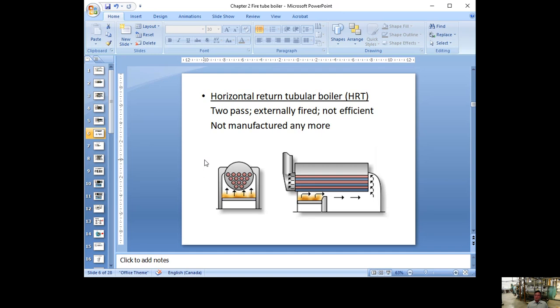What they mean by 'externally fired' is that the fire is on the outside — only on one side is there water, and on the other three sides there's no water. So heat is lost to the surroundings; it's not really efficient. You could say this is a two-pass design, but not very efficient. So they improved it with a fire box boiler design.